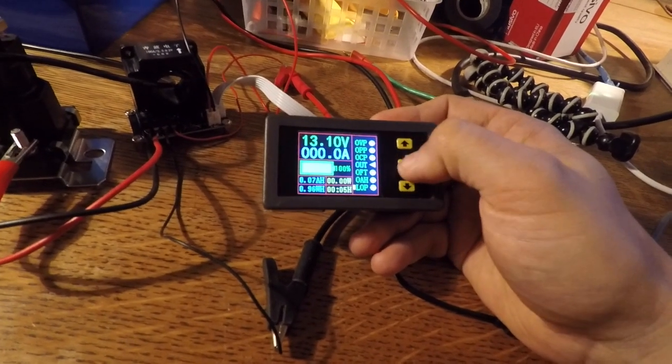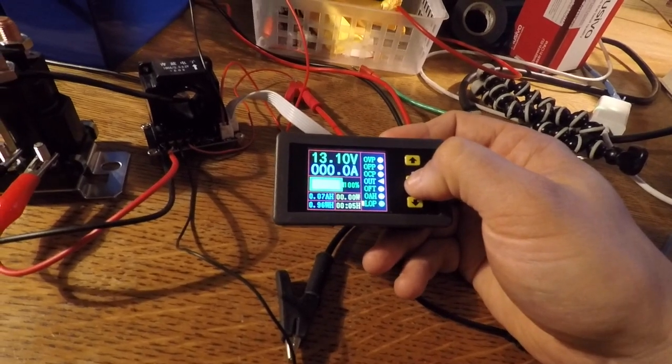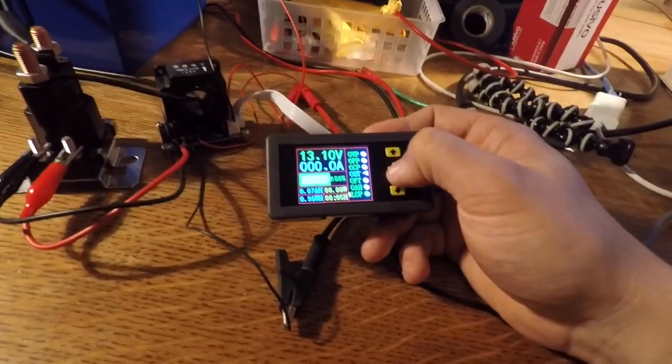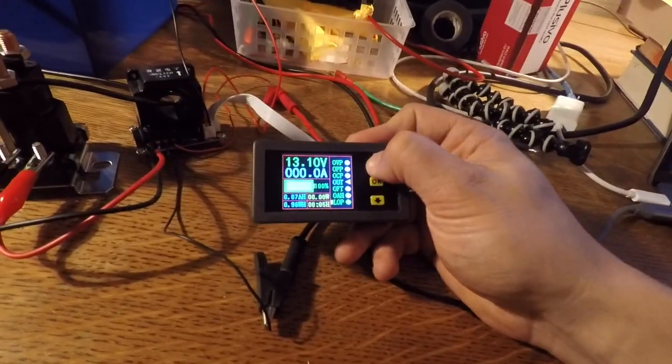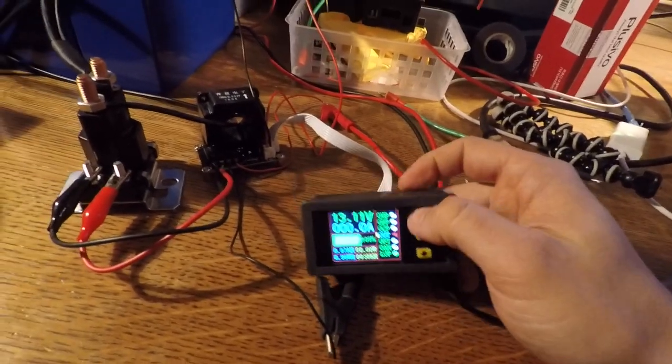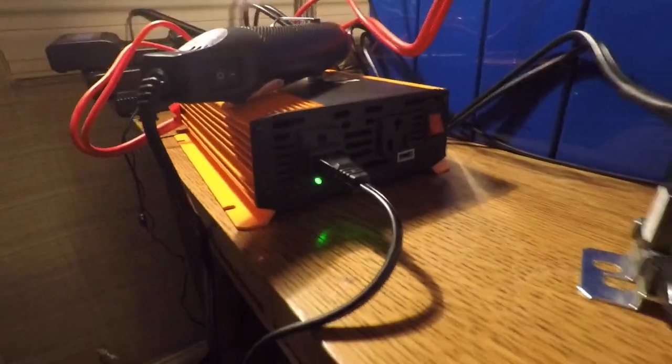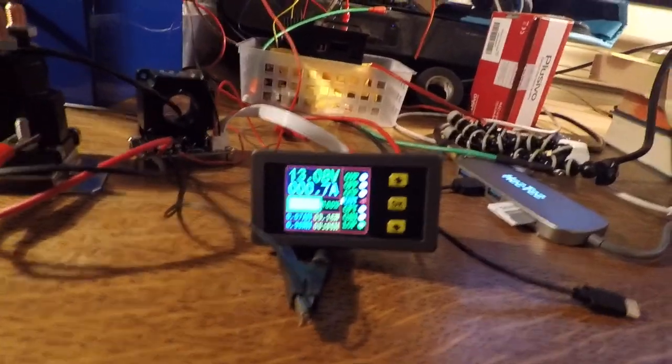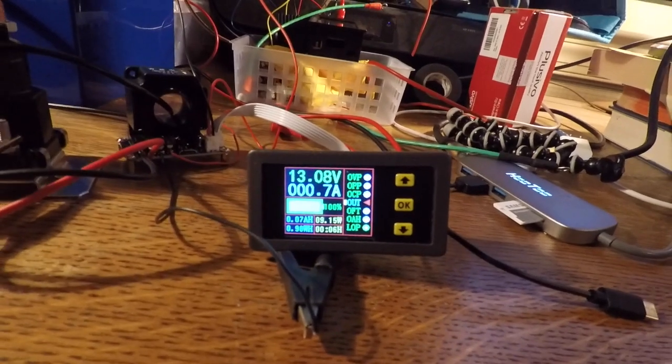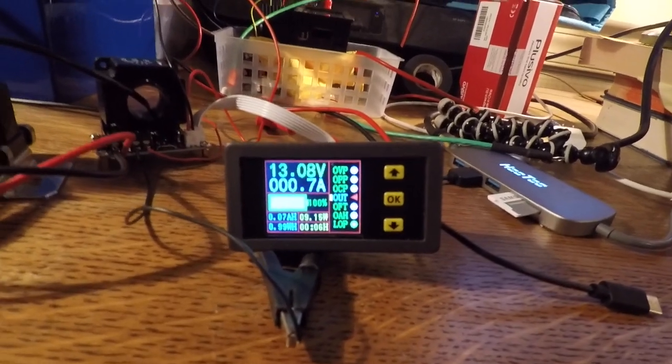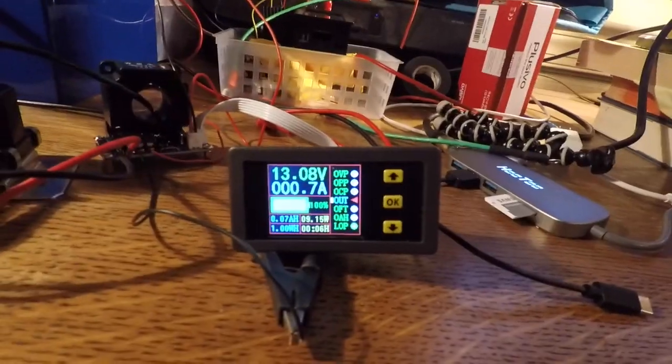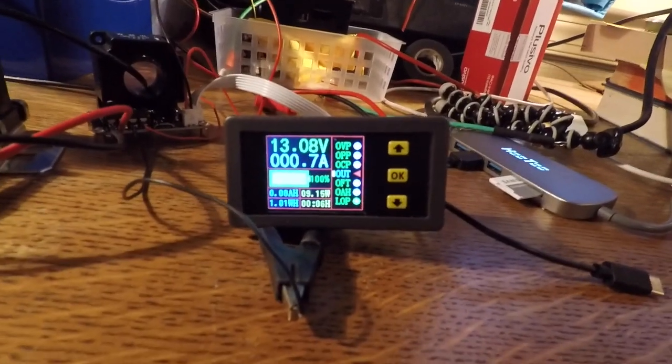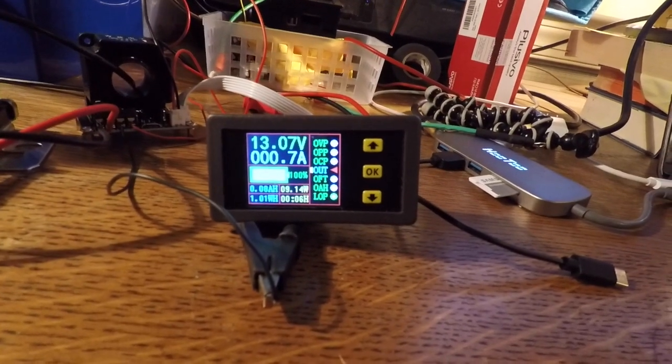So my battery's at 13 volts right now, right? So basically if I turn this on and then I run any sort of power through the inverter, the voltage might dip, and that will probably, if this is working, it should cut off the power to the inverter. So let's try that. So now the inverter's turned on, you can hear it. Let's turn the inverter on. Now the inverter's on. And you can see we're at 13 volts, just above 13 volts, and we're pulling a little less than an amp, which I know is accurate. And let's go for it. I'm going to turn on the power. We're going to dip below 13 volts. And if things go well, the low voltage protection should kick in, and the inverter should get cut off, and the contactor should get turned off.